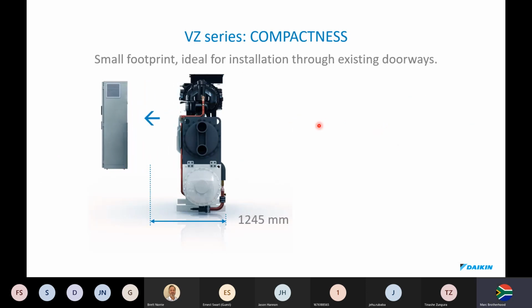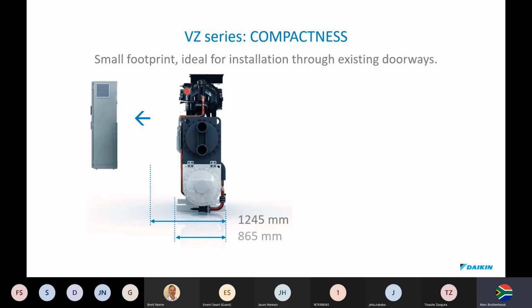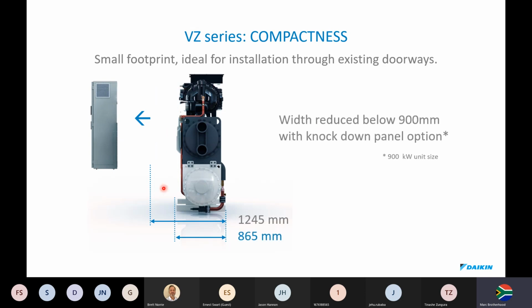This is a very unique feature of the single circuit chiller. This is ideal for retrofitting existing plant rooms. This will actually slide through a normal door. Even a door in your house, this chiller, as big as it is, we take off these 4 bolts that hold this electricity box on and a plugged wire. You remove this pigtail, the box comes off, you put this on a dolly, and you slide this right through a door.